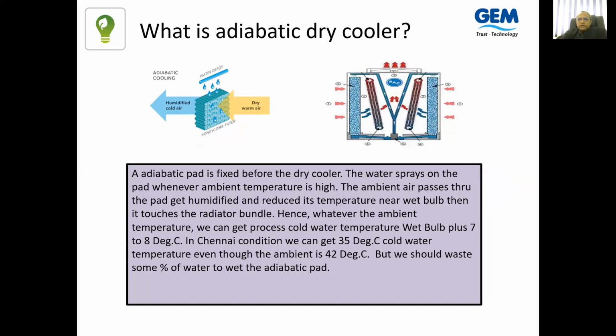Now the recent concept is to use adiabatic. So this adiabatic system is a retrofit to the dry cooler. This adiabatic pad, by evaporating some amount of water in peak summer, will ensure the evaporated water reduces the air temperature from the entry point to the cooler inlet, and can maintain a temperature of about 34 to 35 continuously, depending on even the highest ambient.